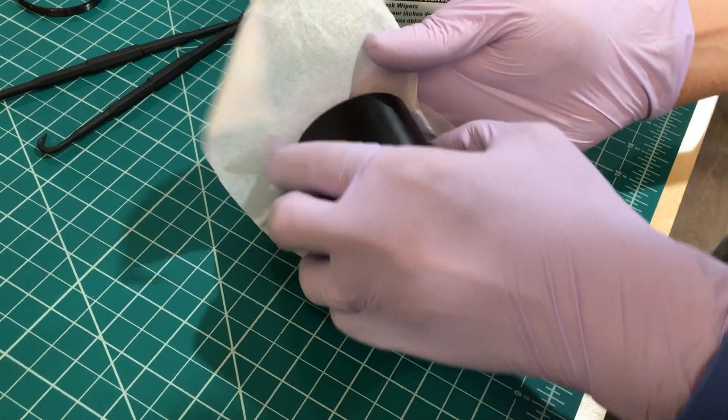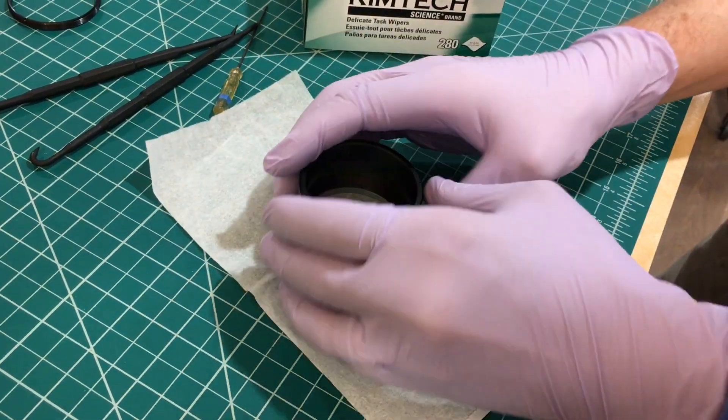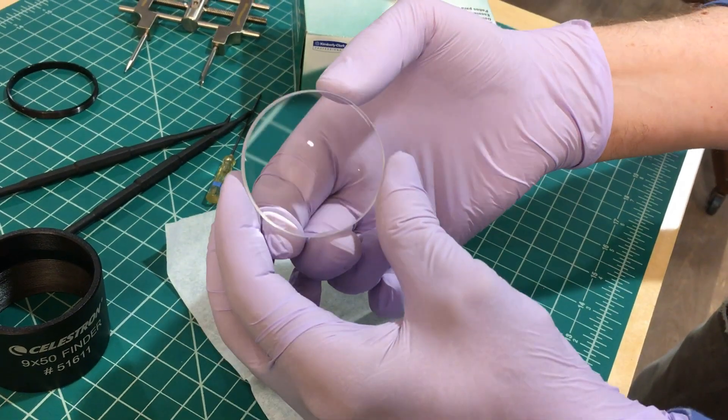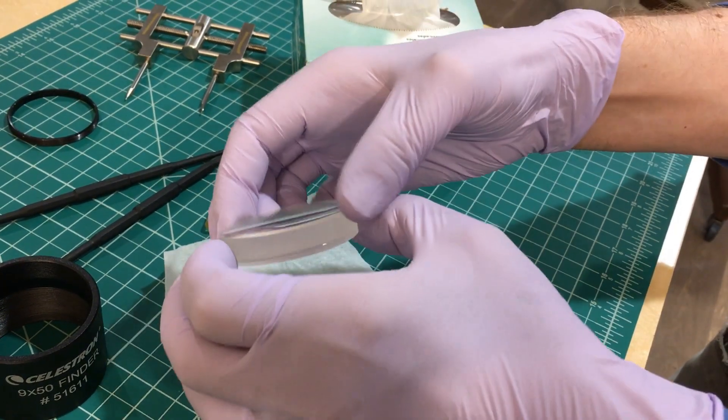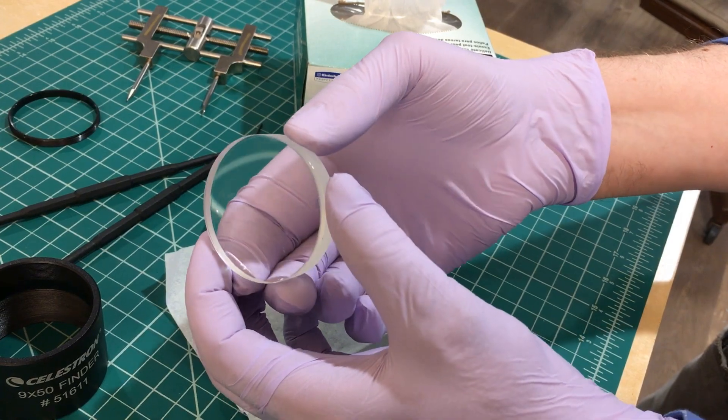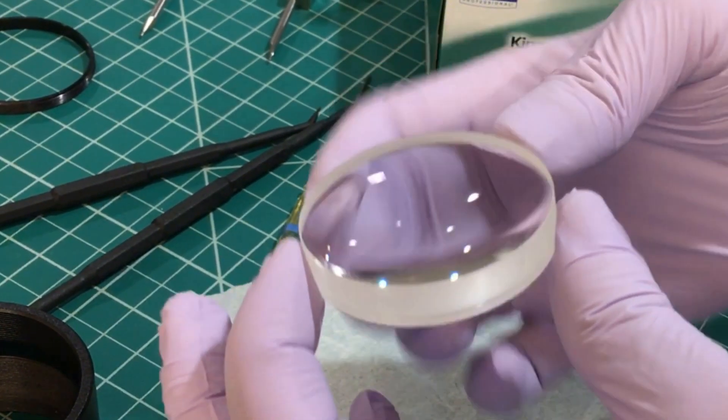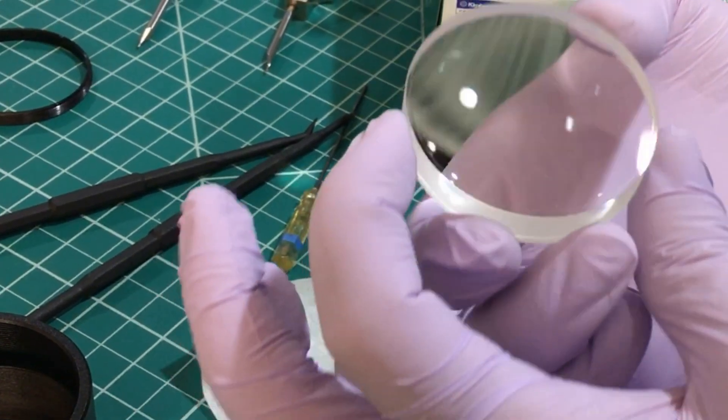Visual inspection shows that this lens looks pretty good cosmetically. Using reflections from the room lights, we see that it's clean and without scratches. The anti-reflection coating is in good condition. We don't see any smears or fingerprints. Here you can see the interface where the two components of the doublet are cemented. This lens is likely well corrected for spherical aberration.